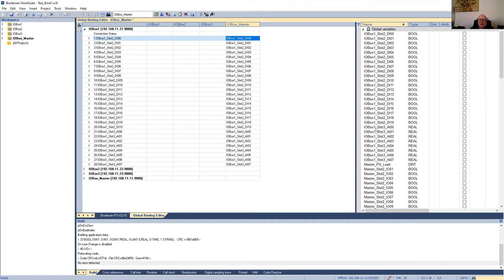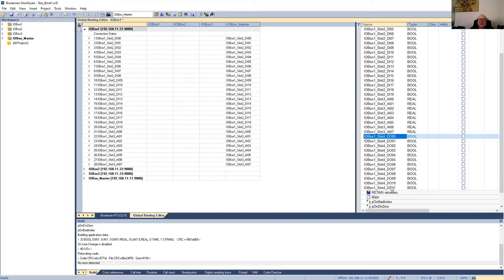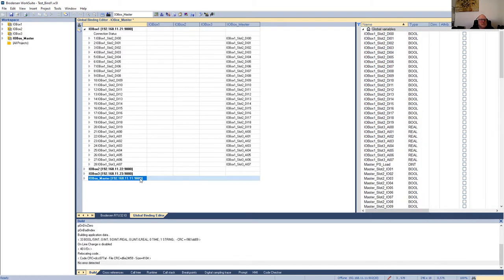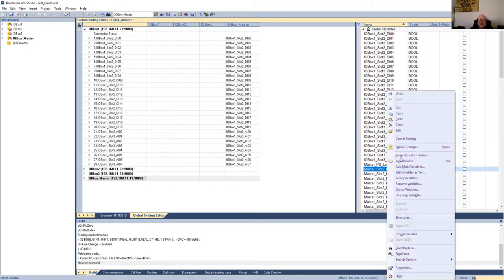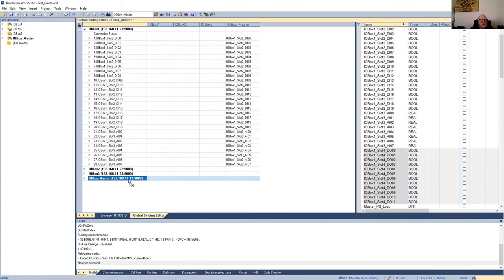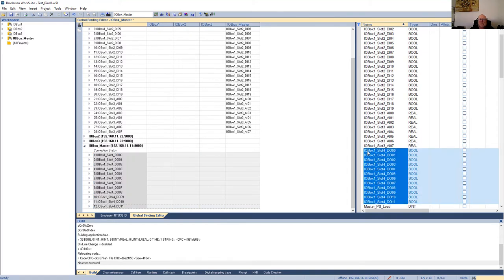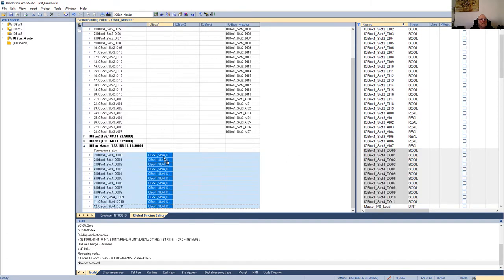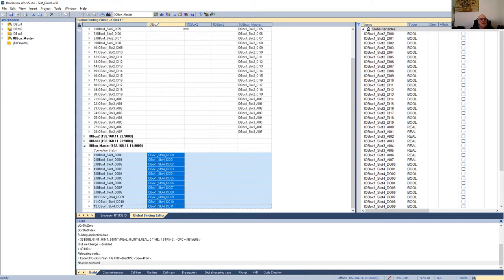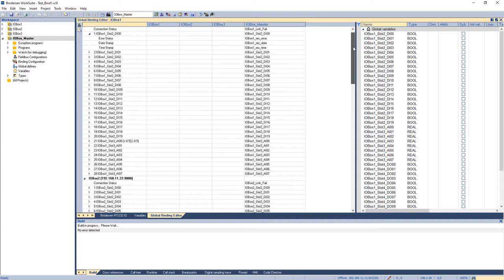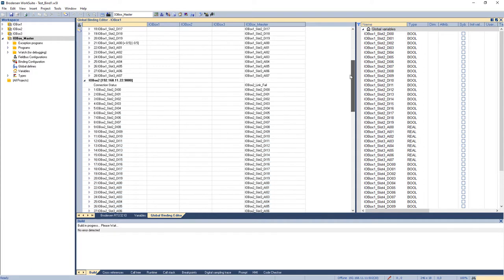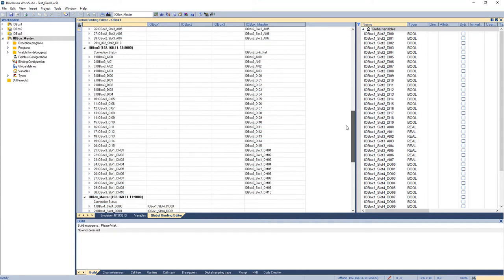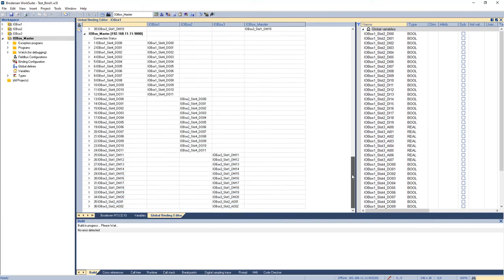If we look at outputs, they work in the opposite direction. Go back to I/O Box 1, I highlight some outputs, I'm going to copy them. The master needs to have an image of those variables. So again click anywhere, paste in those variable names. This time I'm going to ask the master to publish those output variables. And they also need to have a destination. So we're going to take them from the master and we're going to write them to I/O Box 1. We've now done all that replication. We have I/O Box 1 with its input variables being published, I/O Box 2, I/O Box 3.